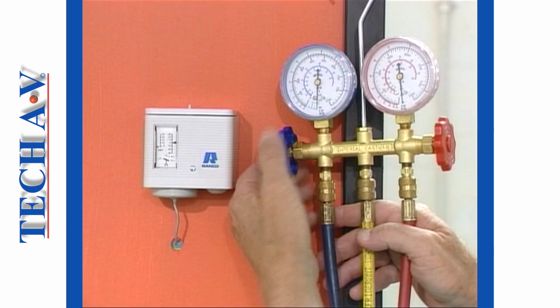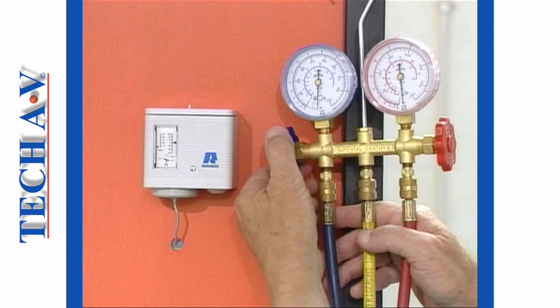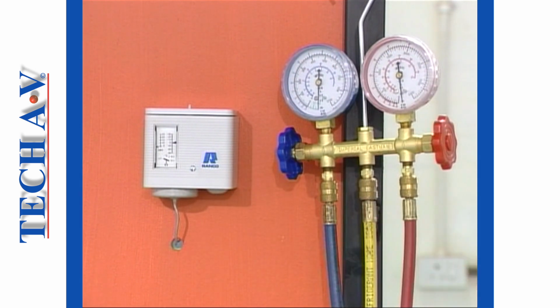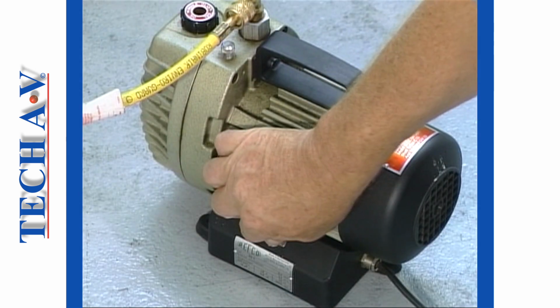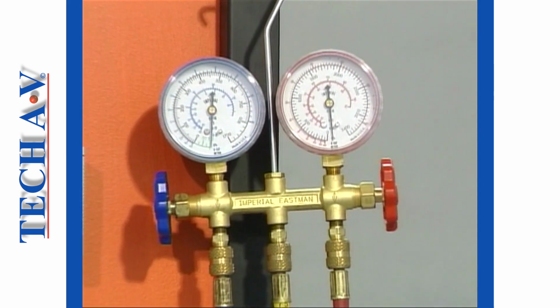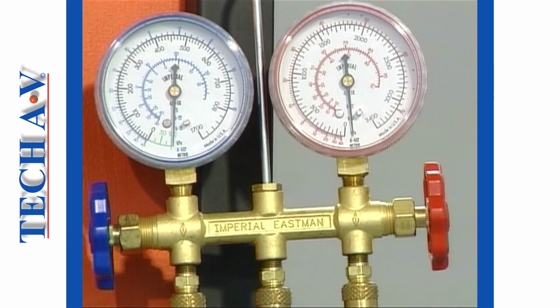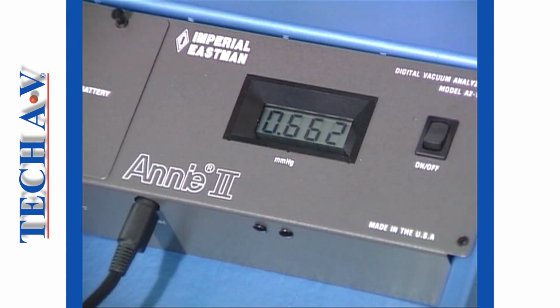Upon achieving the lowest vacuum possible, close off the hand control valves and shut down the pump. Then leave the system standing in a vacuum. The pressure may rise a little once the pump is switched off. The manner in which the analyzer reacts provides clues as to the system condition.